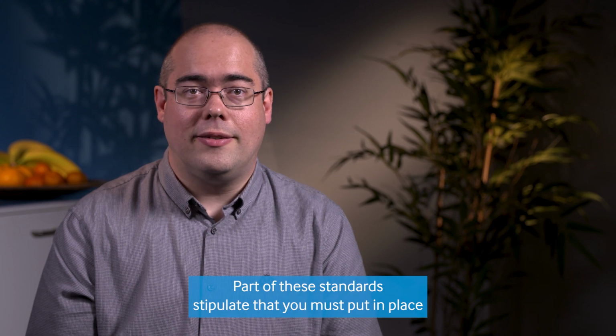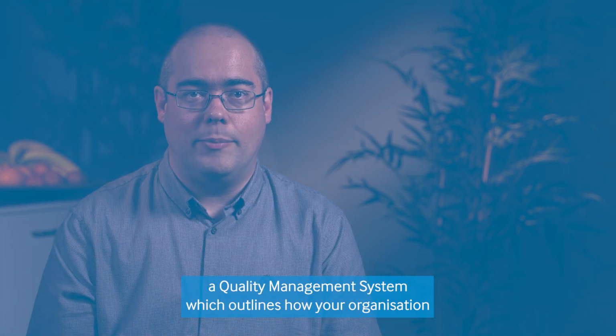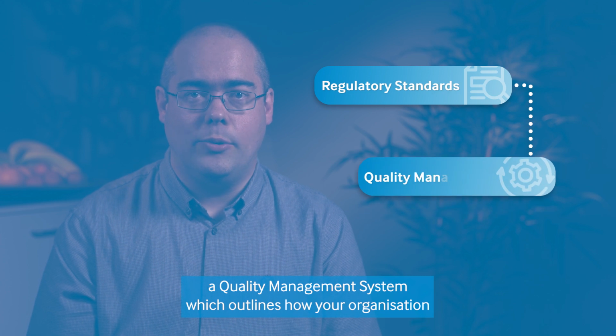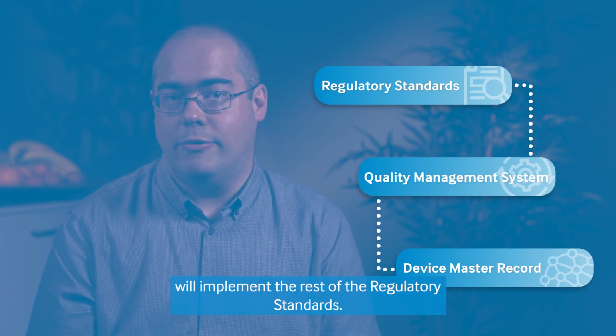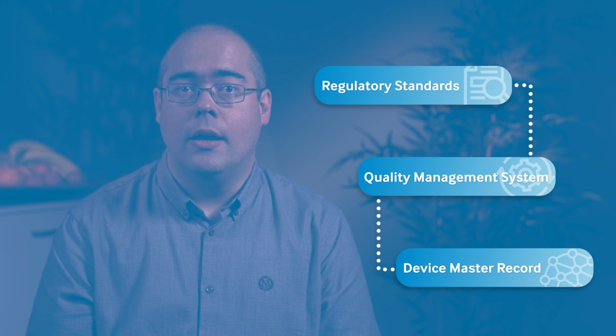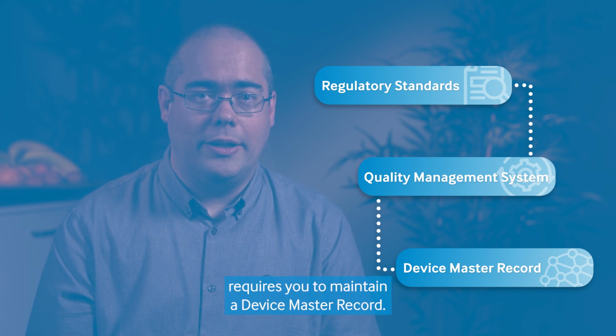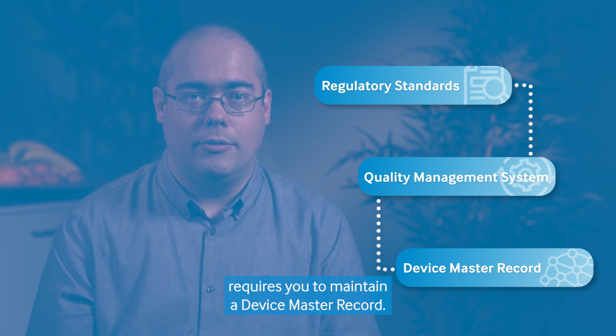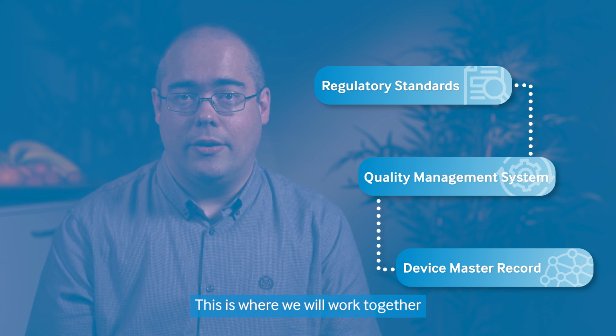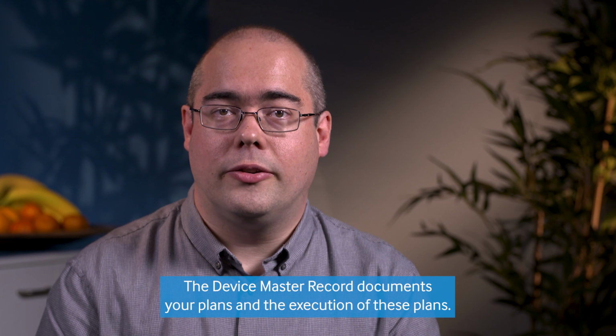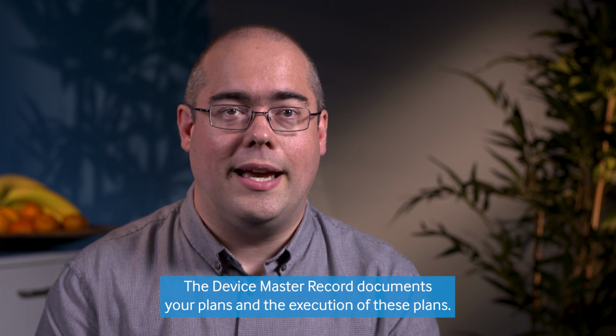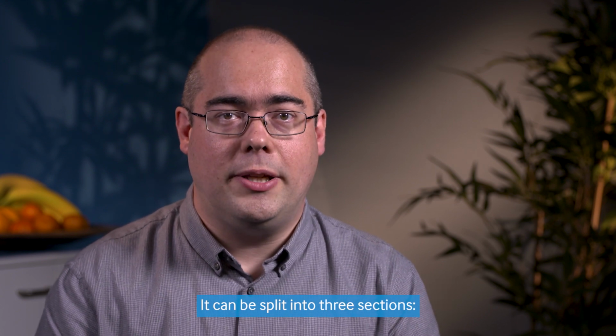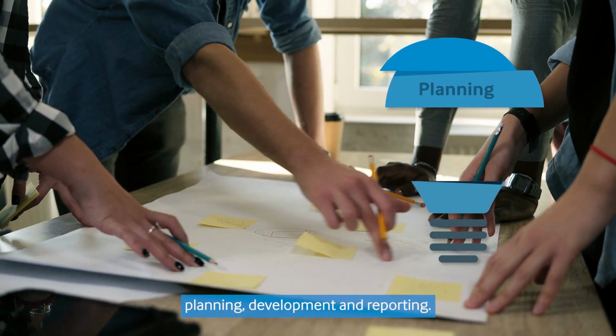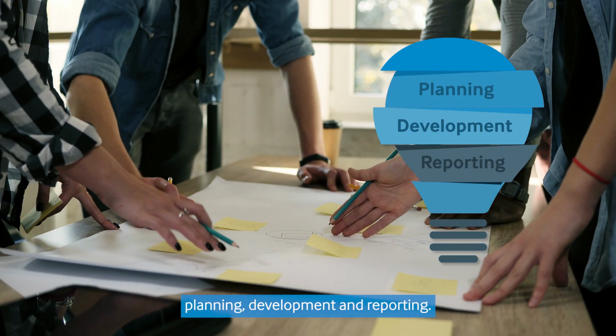Part of these standards stipulate that you must put in place a quality management system, which outlines how your organisation will implement the rest of the regulatory standards. The quality management system requires you to maintain a device master record. This is where we will work together, and what I'm going to talk to you about in this video. The device master record documents your plans and the execution of these plans. It can be split into 3 sections: planning, development, and reporting.